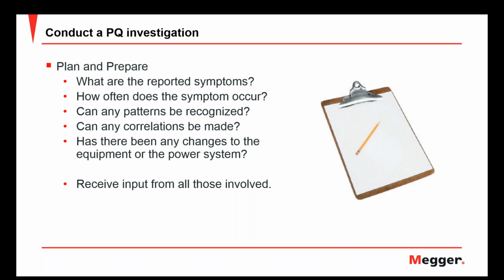Do we see any pattern with it? Are they always happening pretty much at the same time of day? That could be indicative of a piece of equipment turning on. Can we make any correlations? Big question is, has there been any changes made to the facility lately? Because that can be a clue as to something that has changed, that's causing a problem.